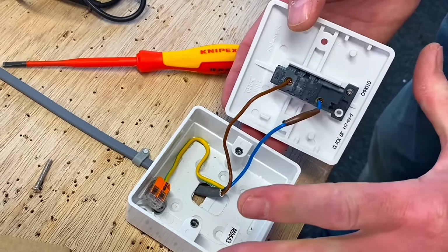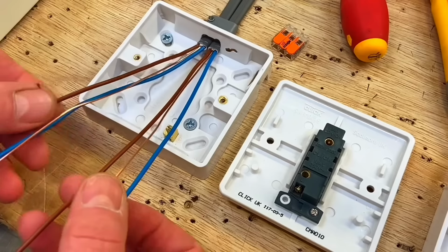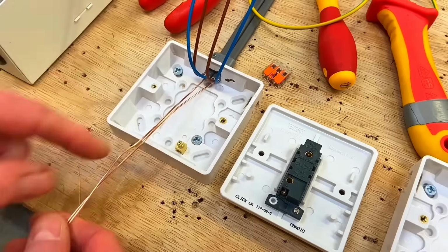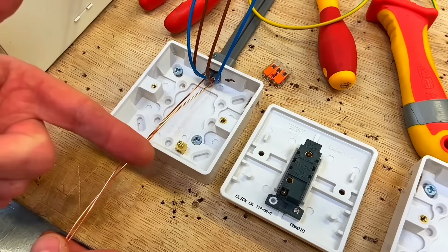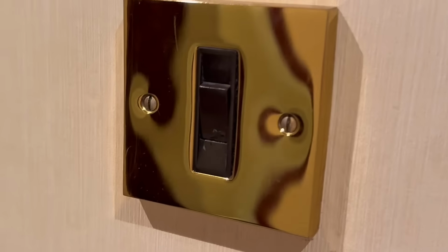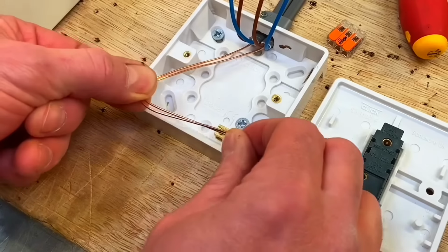In this case, where the feed has been taken to the switch, doing the 2-plate method, both the blue conductors are actually neutrals. Concentrate on connecting the CPCs. We've got an insulated box and an insulated switch, so we don't need a CPC. We'd need it if there was an exposed conductive part, a metallic light switch, etc. However, we're still going to need it as part of the circuit and further upstream, so we're going to connect them in the back of the actual switch itself.